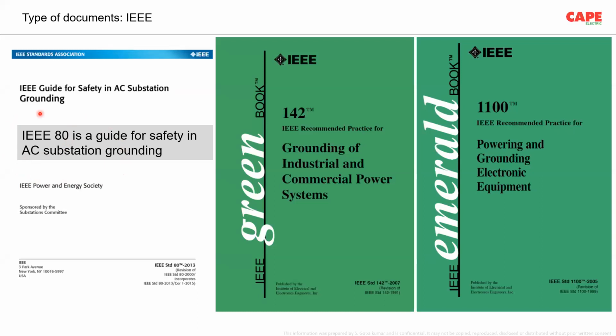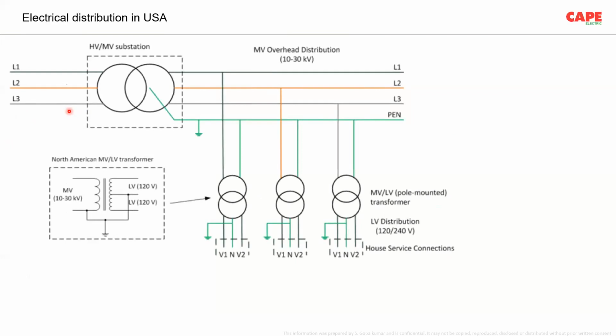Recently, I have seen a tender from railways, one of the largest projects upcoming in India. They have a signaling and telecommunication installation. In a signaling and telecommunication installation, you can very well see that the application is only maximum 400 volt, and all the rest of the installations are lesser than 400 volt. And they wanted to make earthing as per IEEE 80, which is absolutely wrong. Now, how this IEEE 80 is used, very important. In America, they have high voltage or medium voltage distribution, say for example, 25 kV.